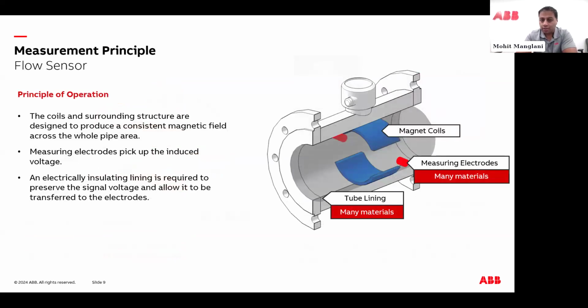In terms of what it looks like, I don't know if you guys can see my mouse, but basically it's a spool piece. It's a piece of pipe, typically Schedule 40 for most ANSI 150 applications. You've got flanges on the side. You have coils on the top and the bottom that generate your magnetic field. You have metallic electrodes that capture that voltage. And usually on the inside of the line, you'll have a non-conductive material, whether it be rubber, Teflon, PFA, ceramic, etc. I won't go into all the materials. But the idea is that this is a basic mag meter in terms of what it's made of and what it looks like on the inside.